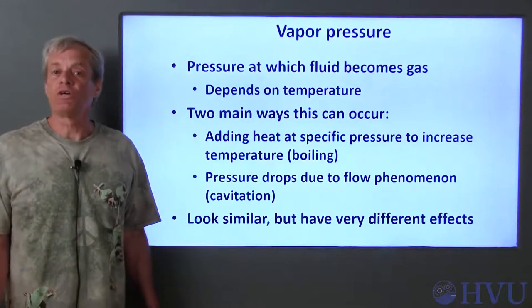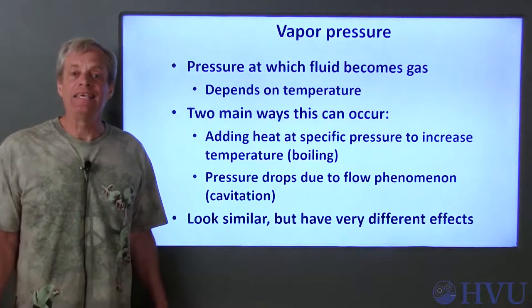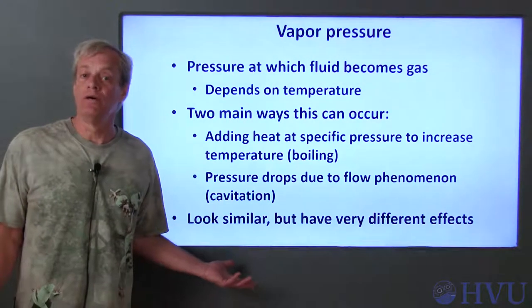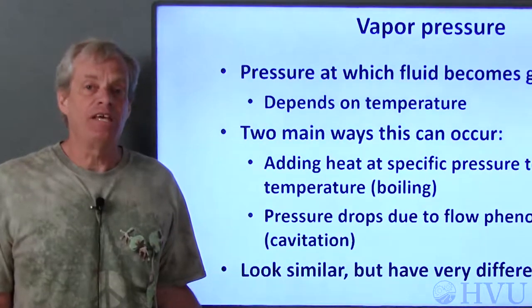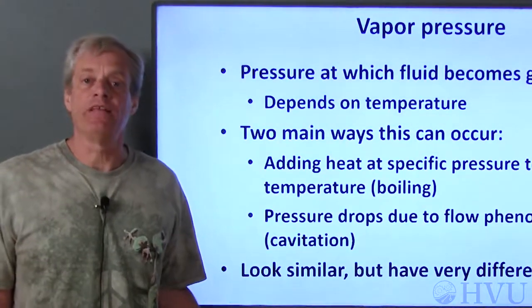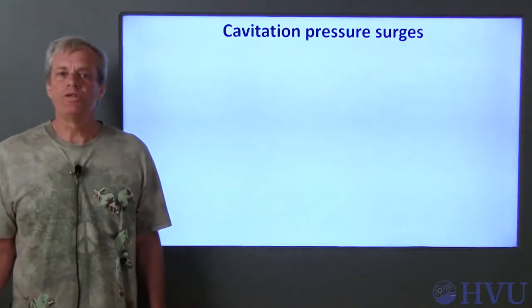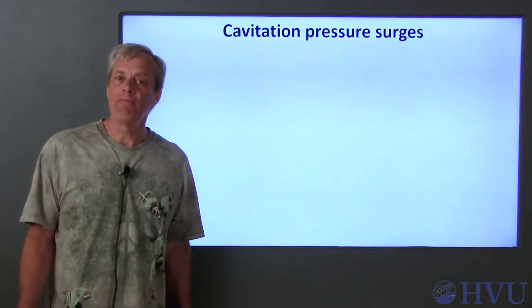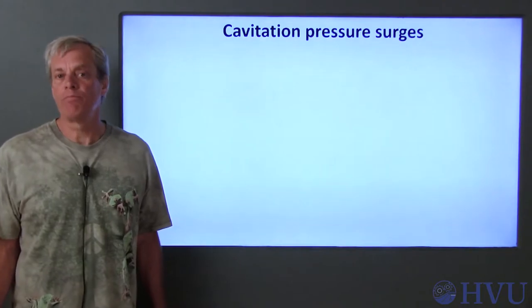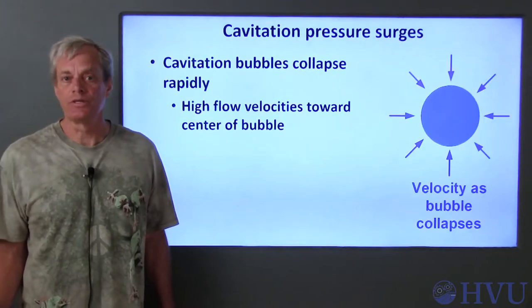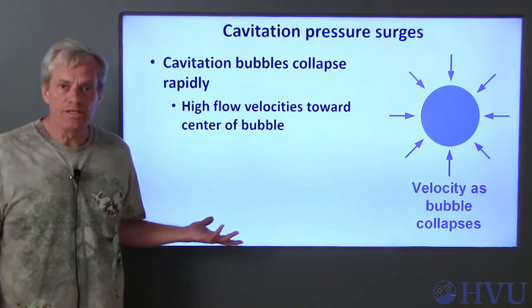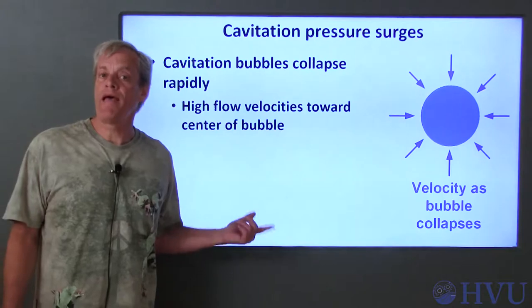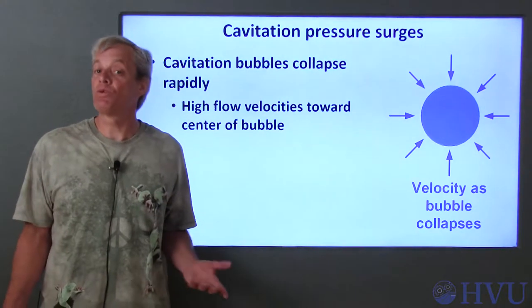The main difference is that the bubbles caused by adding heat to the water tend to collapse slowly. Cavitation bubbles, on the other hand, collapse quickly. When bubbles created by cavitation collapse, they can create very high pressure surges. The reason for this is that cavitation bubbles tend to form and collapse quickly.